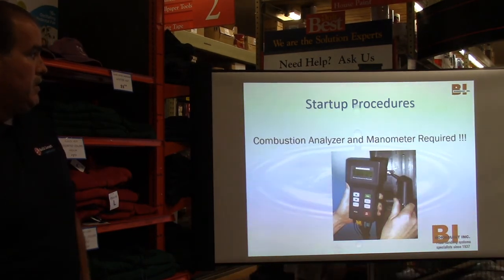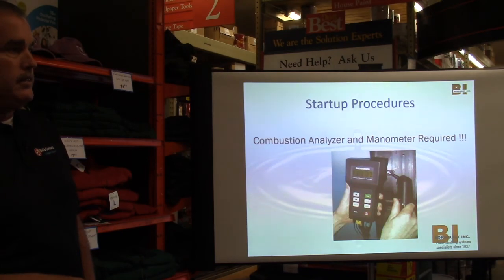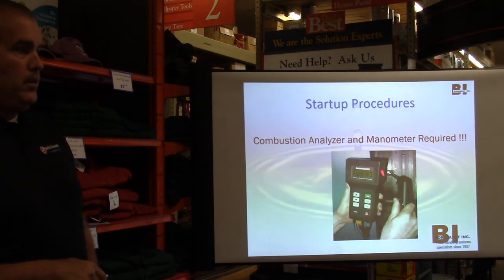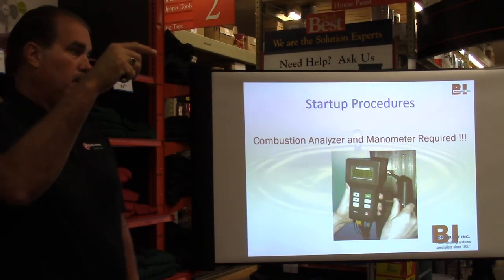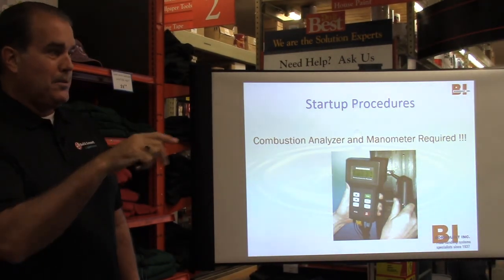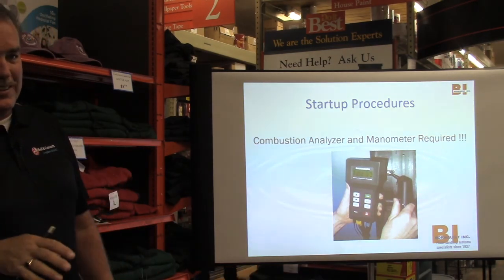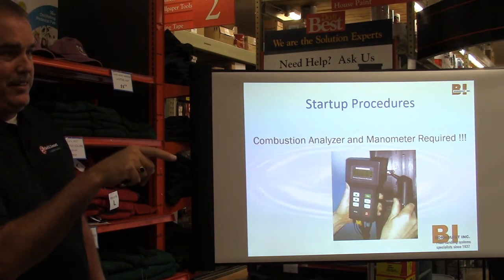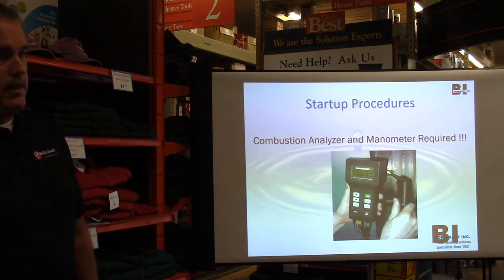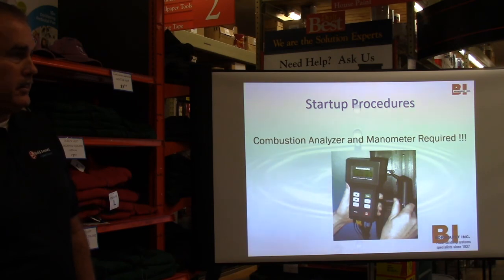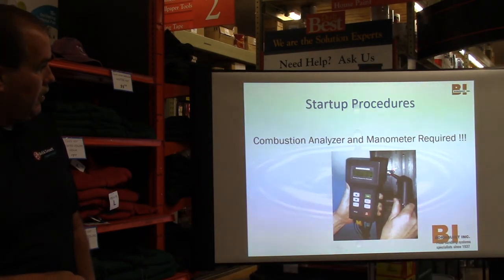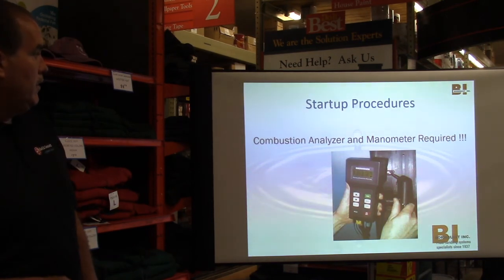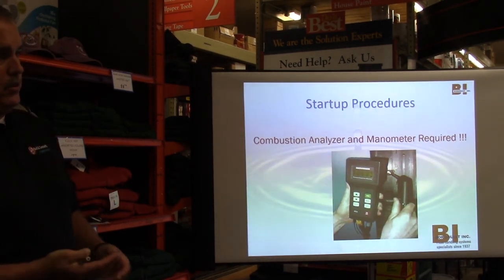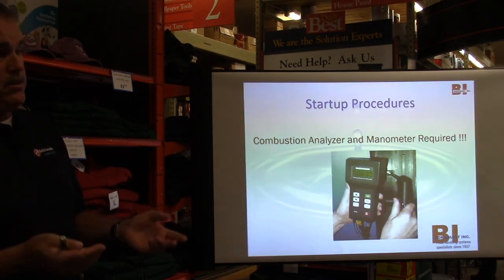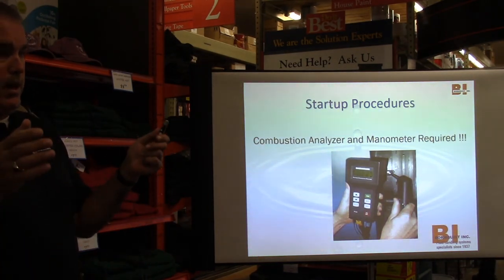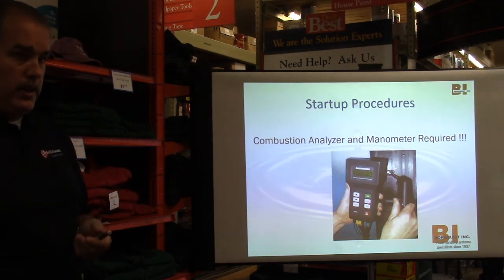What I really want to bring out is that piece of equipment I was talking about, the analyzer. They do stick it right in the flue, just past the outlet of the boiler. That's where they're measuring. So they'll drill a little hole, and don't be upset if they drill a hole in your vent, because they need it to stick the analyzer in. Then they'll put a piece of tape over it or something to plug it so that the flue gas doesn't get into the room. They're basically measuring O2 or CO2, and they can measure other things too, but that's for the most part. The manufacturer will have a parameter they want to operate within, and they're just checking it.